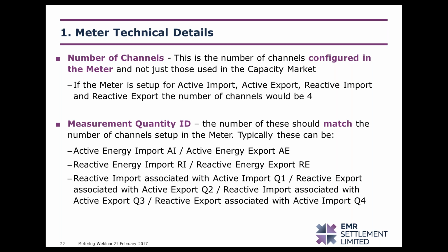The measurement quantity ID and the number of channels are linked. There should be a measurement quantity ID for each one of the channels that have been listed in the previous entry. The measurement quantity ID will identify what type of energy a half-hourly channel has been configured to record. I've included typical examples in modern metering of what we would expect to see. So in the previous example, where I said there were 4 channels set up in the meter, there should be 4 measurement quantity IDs listed, and these would be active import, active export, reactive import, and reactive export. Any mismatch between the number of channels and the reported measurement quantity IDs will result in a failed metering test.